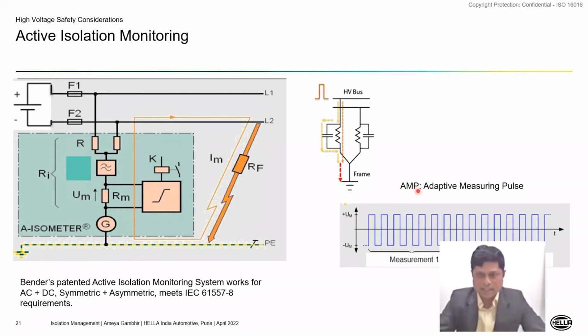They call it AMP, the adaptive measuring pulse. This generator creates an impulse that is fed into the line. If there's a leakage resistance between either line and chassis, or both lines to chassis, the same signal is measured back by the system. It uses internal filters to avoid the effects of 50 or 60 hertz noise, or switching noise from DC-DC converters or inverters, allowing it to accurately estimate the isolation resistance.